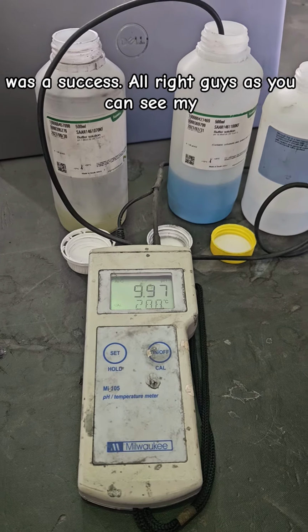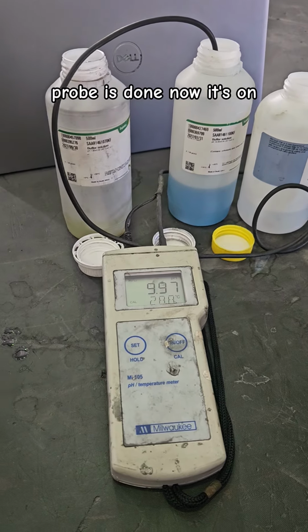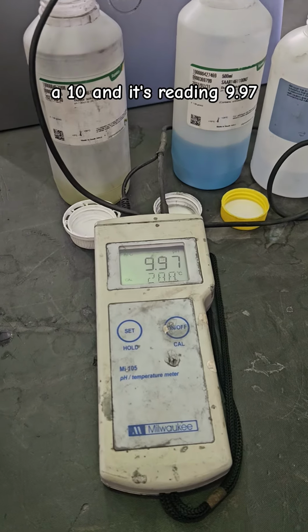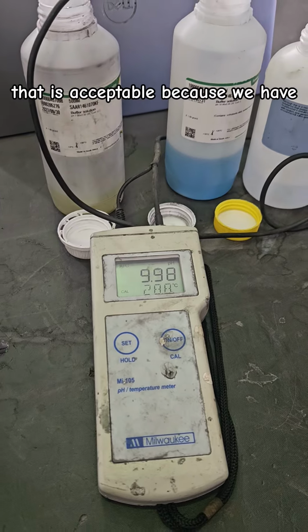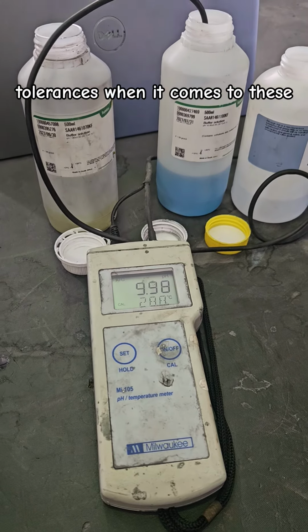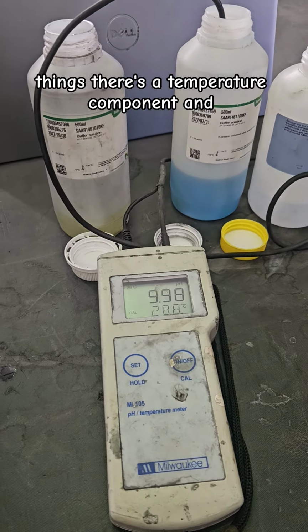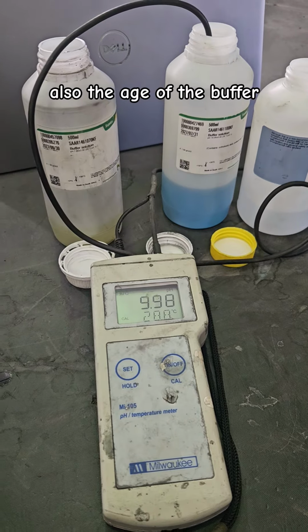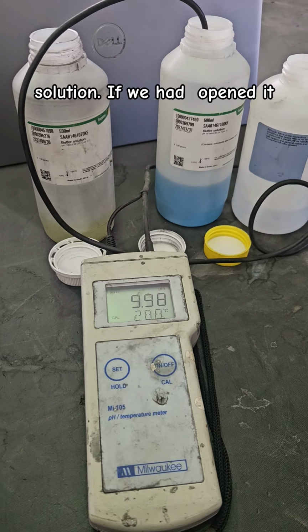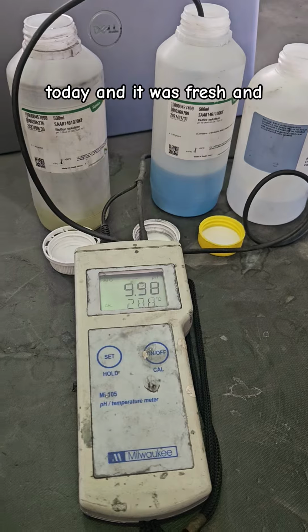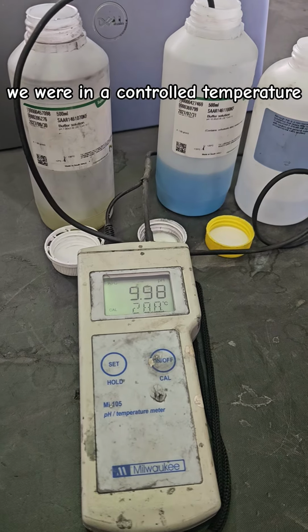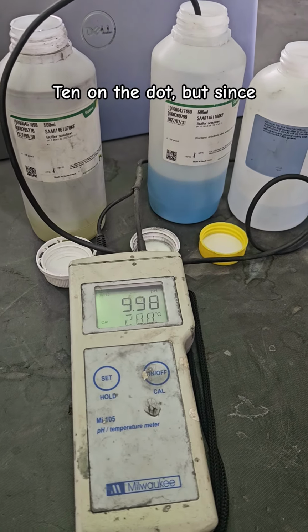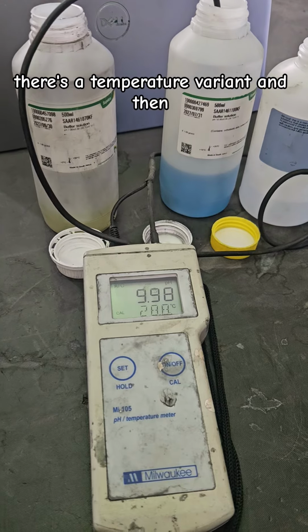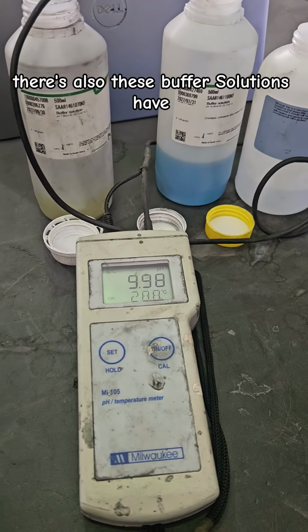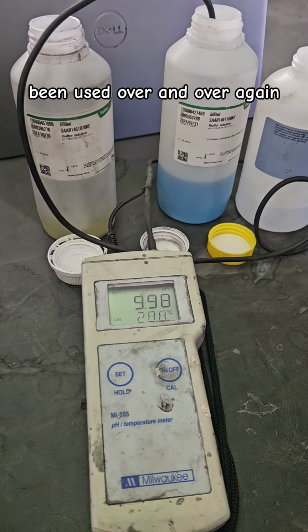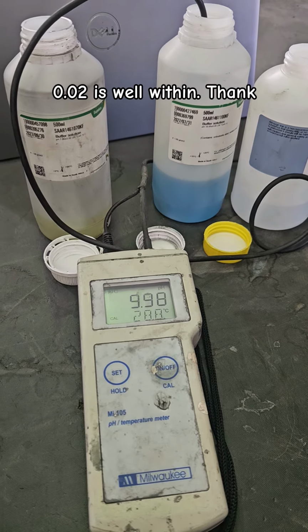Alright guys, as you can see, my probe is done now. It's on a 10 and it's reading 9.97. That is acceptable because we have tolerances when it comes to these things. There's a temperature component and also the age of the buffer solution. If we opened it today and it was fresh and we were in a controlled temperature environment, we were likely to get 10 on the dot. But since there's a temperature component and then there's also these buffer solutions have been used over and over again, there will be that tolerance. But 0.02 is well within tolerance.